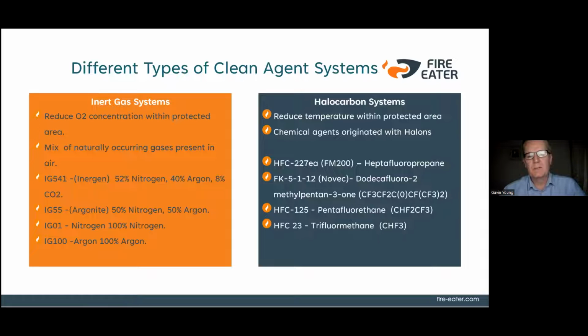Halocarbons then are a chemical gas. They're stored as a liquid, and they extinguish a fire by reacting with the fire and essentially reducing the temperature. The chemical makeup of the gases is there in front of you. HFC 227ea, which is a common brand called FM200. Also, the other most common brand in the marketplace at the moment is FK-5-1-12, which is Novec. HFC 125 and HFC 23 are generally not used in Ireland.